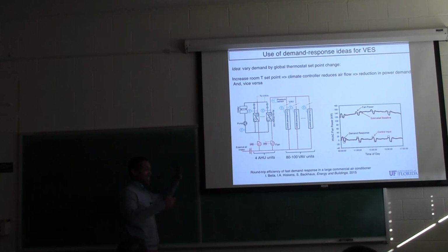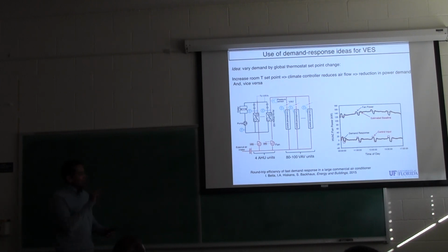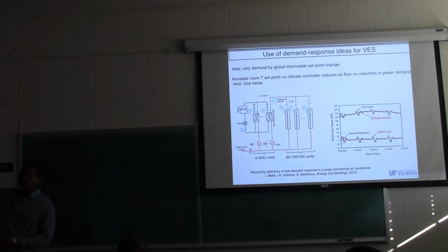So it's kind of bold to think about what they did. They went to this large building with about 100 VAV units. What they did was write software to remotely change all the temperature set points of all 100 VAV boxes. Every zone has a local controller, called a VAV box controller, where you enter the set point.